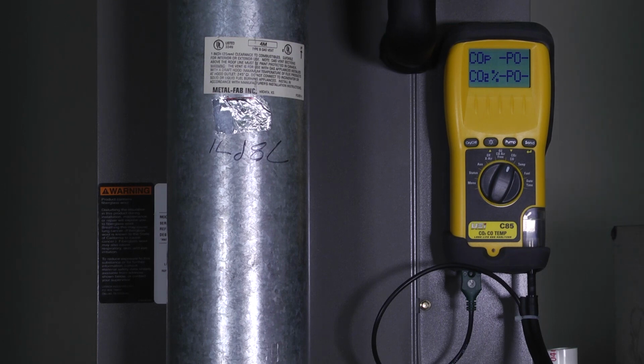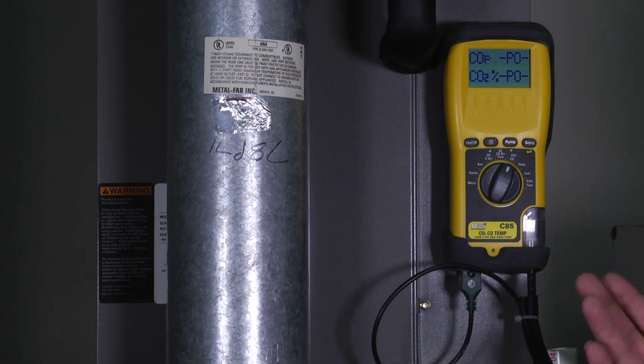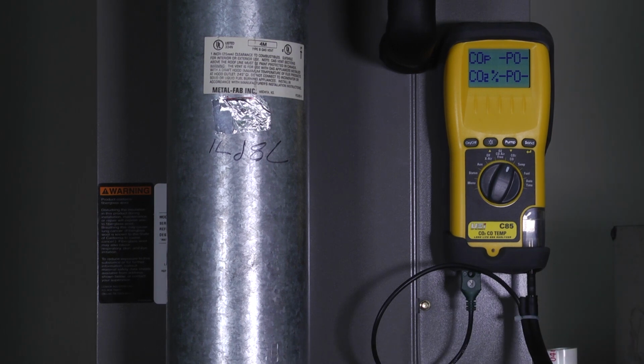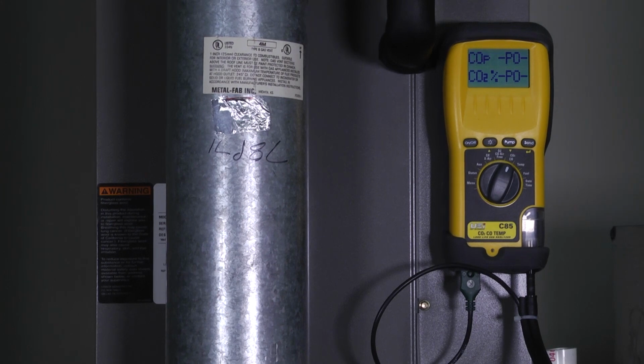But my flue gas analyzer is going to tell me what's happening in the system. It's going to tell me if my furnace is producing CO. It's going to tell me if my flue gases are way too high. It's going to tell me some things that I need to look at.